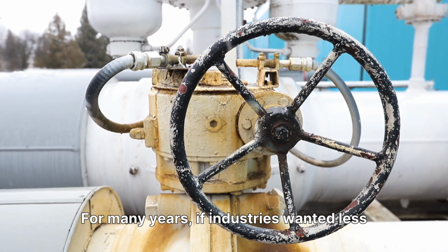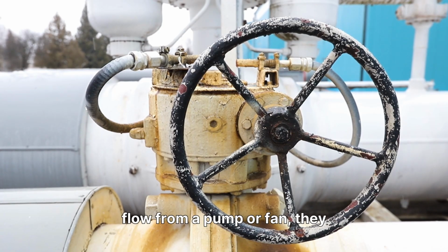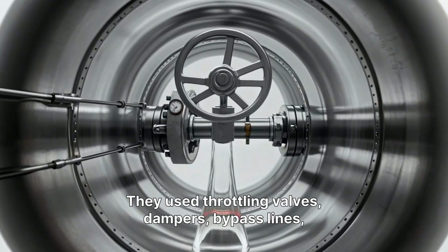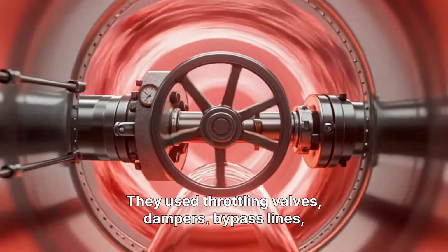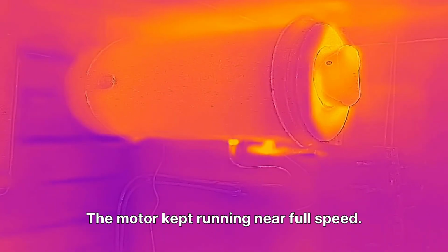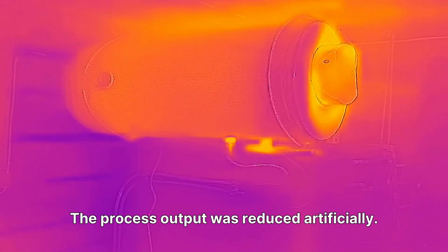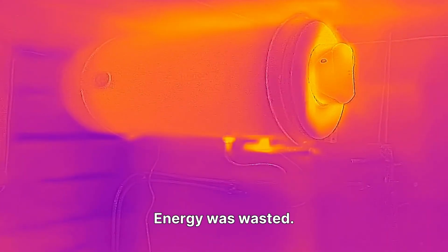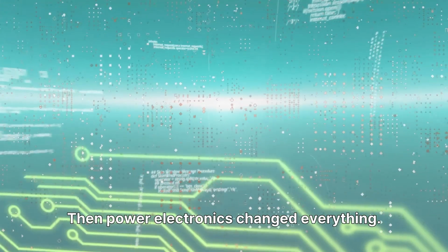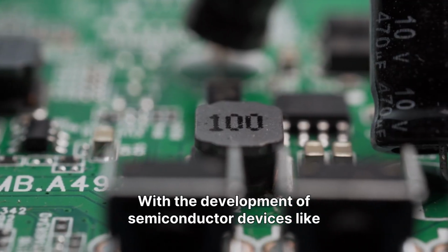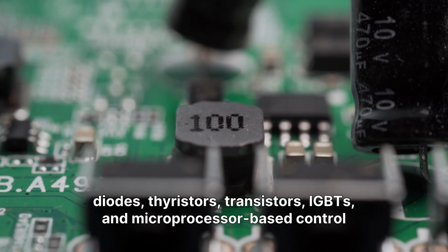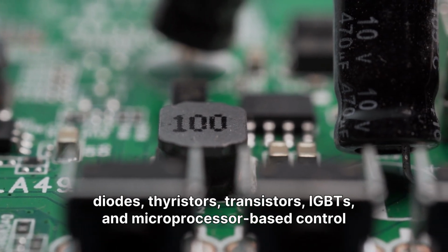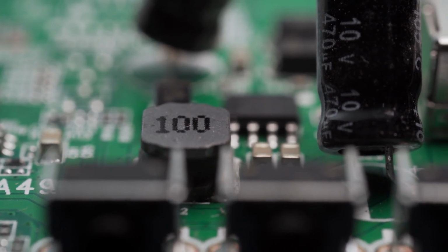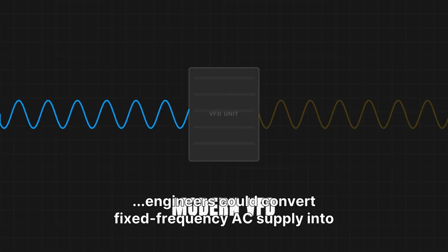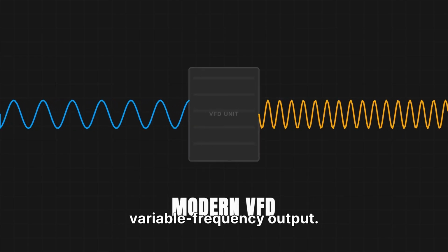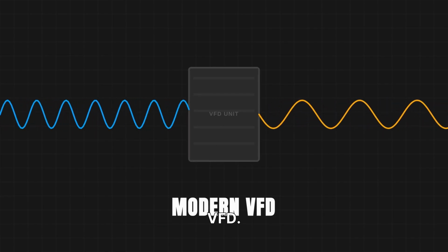For many years, if industries wanted less flow from a pump or fan, they did not slow the motor. They used throttling valves, dampers, bypass lines, and mechanical methods. The motor kept running near full speed. The process output was reduced artificially. Energy was wasted. Then power electronics changed everything. With the development of semiconductor devices like diodes, thyristors, transistors, IGBTs, and microprocessor-based control systems, engineers could convert fixed-frequency AC supply into variable-frequency output. That was the birth of the modern VFD.